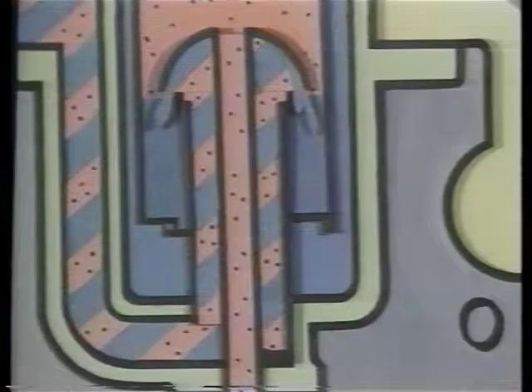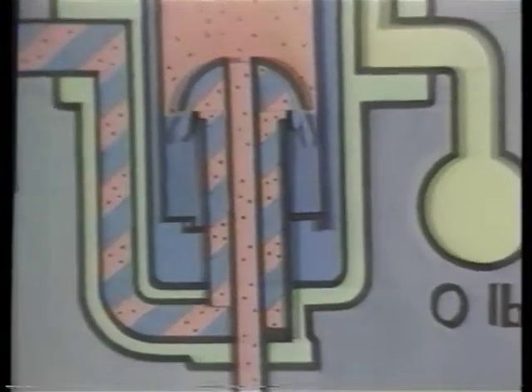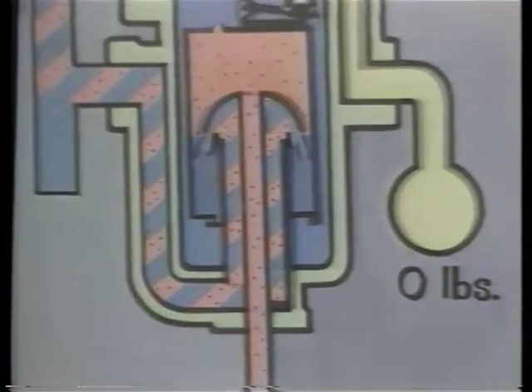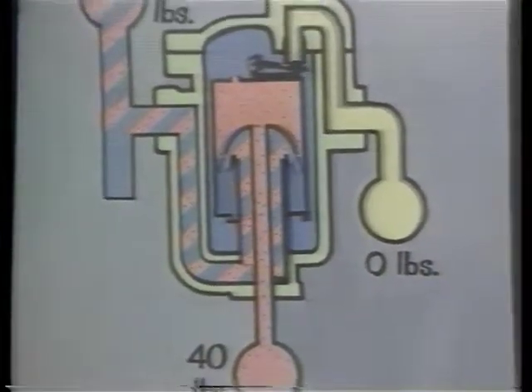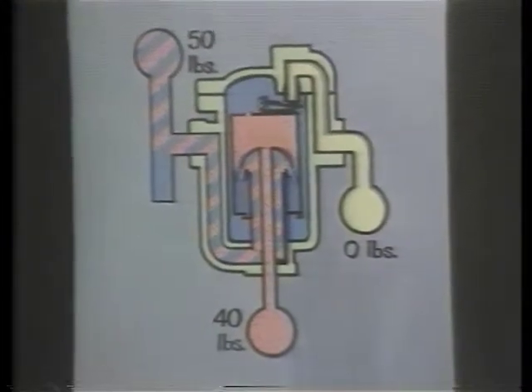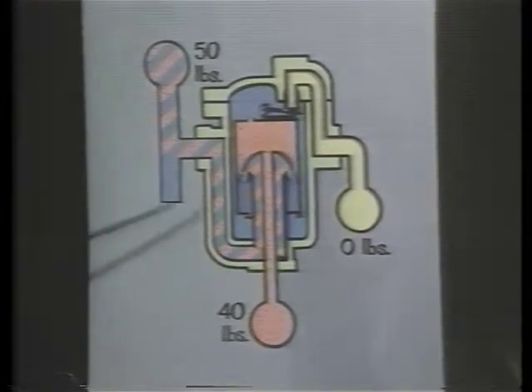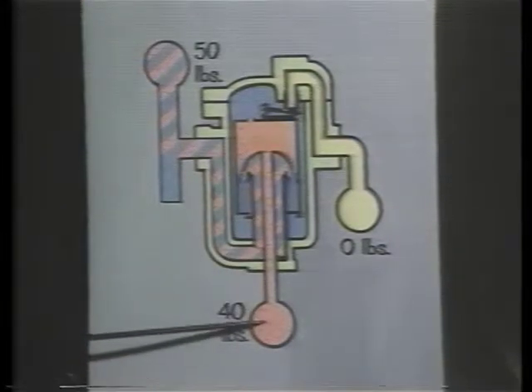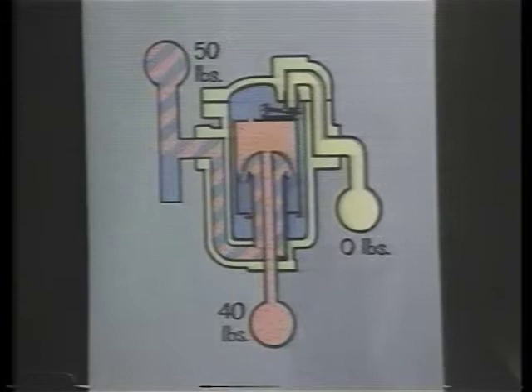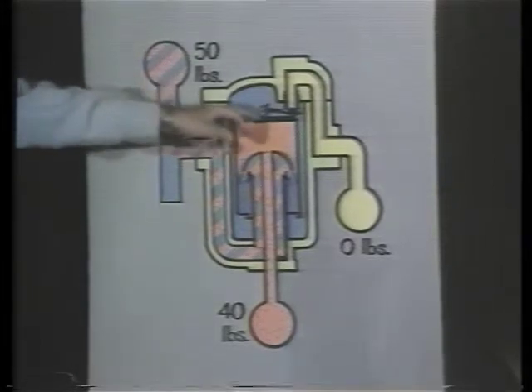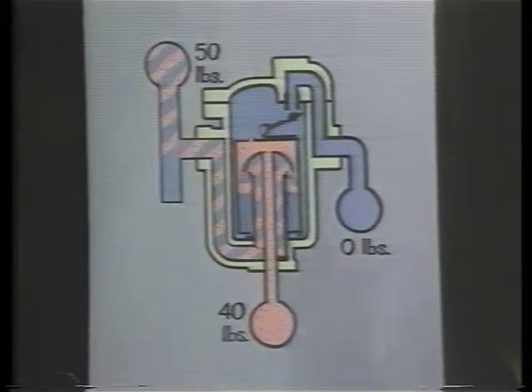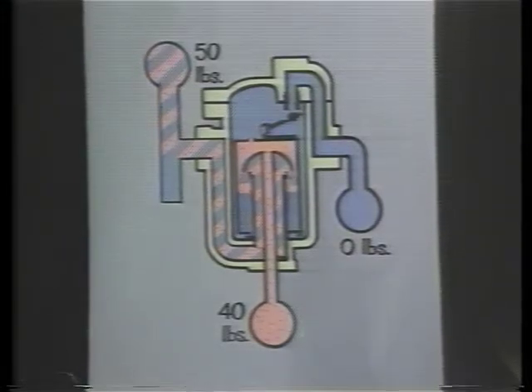On siphon drainage systems, a conventional trap may close prematurely on a false signal caused by flash steam and air. This does not happen with the differential controller, since these vapors are removed from under the inverted bucket. The condensate discharge mechanism continues to function, closing for live steam and opening for condensate. The surging action caused by the intermittent condensate discharge pumps non-condensables and condensate out of the cylinders. The differential controller will automatically adjust the pressure differential across each dryer in response to the load.